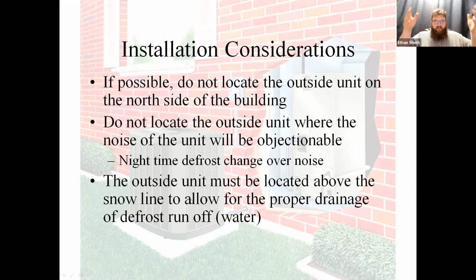That ice will build up on the outside of the unit, and once that coil is encased in ice, the next time it goes into defrost and then goes back into proper operation, it'll generate a little bit of water on the inside of that evaporator, on the inside of that ice shell, and then it'll refreeze that, and then over time it will actually hydraulically collapse the tubing in that outdoor coil. So we see this a lot with Mitsubishi units that aren't put on stands, especially.